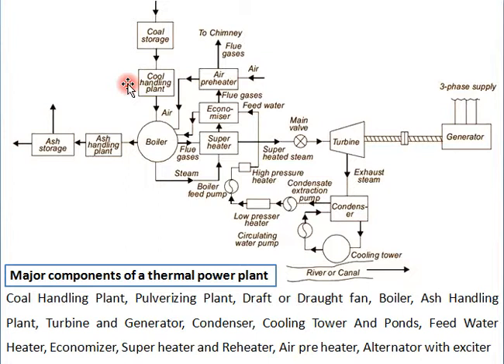When the coal is converted into powder form, it comes to the boiler where combustion takes place. When coal is converted into very small particles, the combustion process becomes very fast or rapid and the combustion of coal becomes efficient. That's why coal pulverization is required.